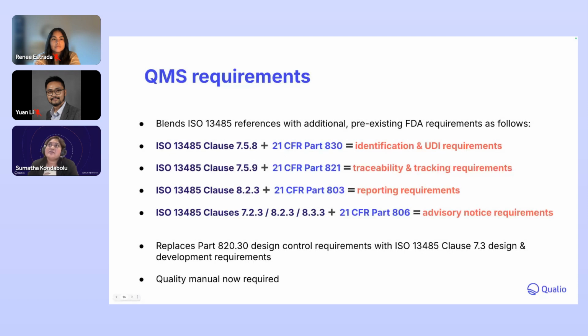The QMS requirements, the quality management system requirements: where there is an incomplete QMS, there is an adulterated device. Ensure you don't neglect those areas where FDA requirements go beyond ISO 13485, for example UDI and regulatory authority reporting processes. Pay special attention to your design controls, as existing QSR requirements are completely replaced by ISO 13485 design controls.